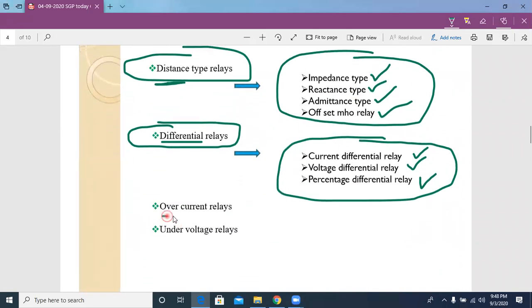So one more is there. One more type is overcurrent relays and undervoltage relays. Here the activating quantity is current, and here the activating quantity of relay is voltage. So overcurrent in the sense, if we consider the activating quantity is current, the relay has a preset value. Suppose the preset value of relay is 1000 amperes, that means 1 kilo ampere.